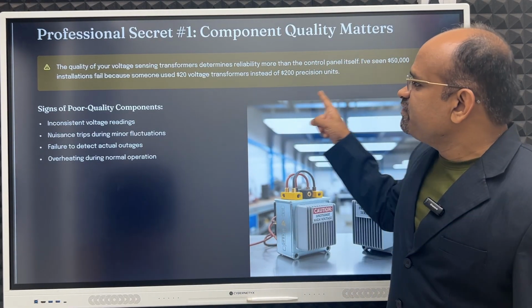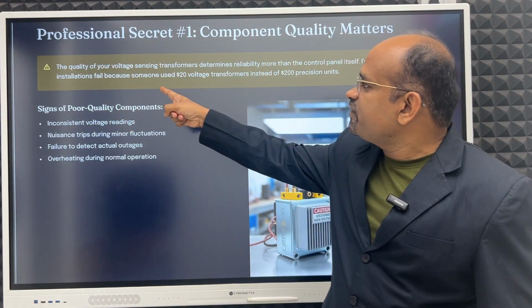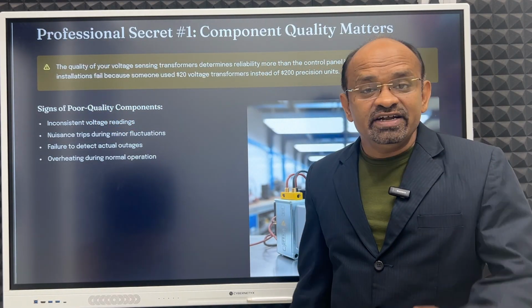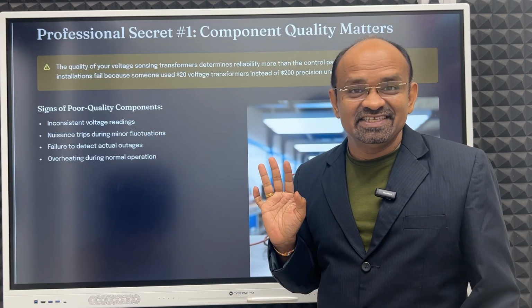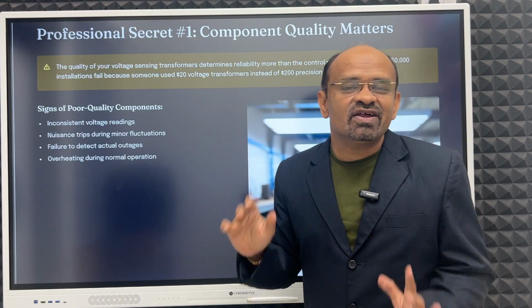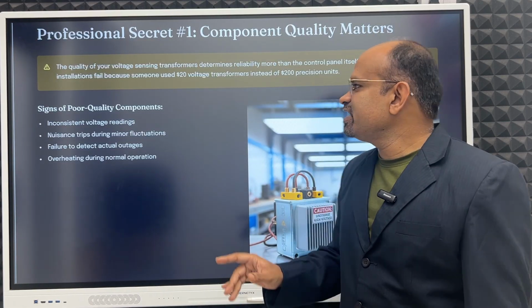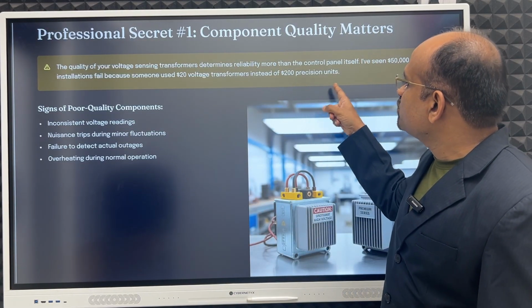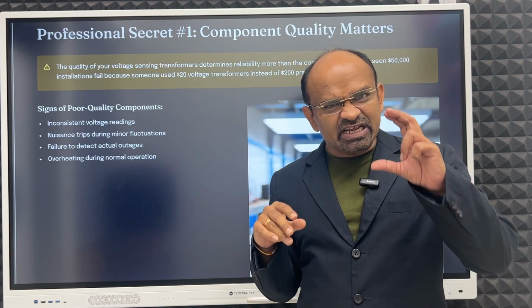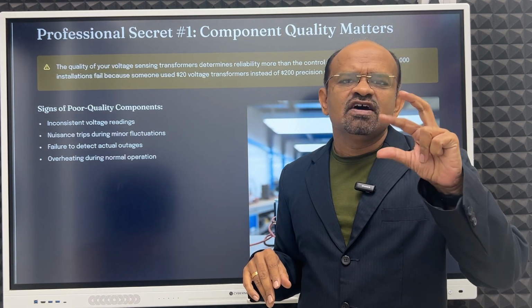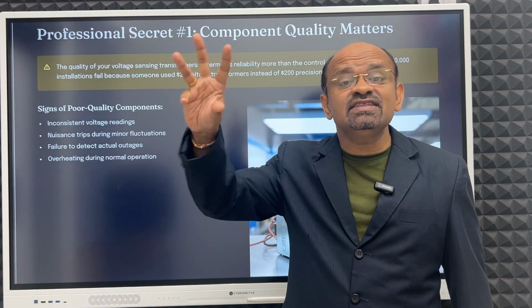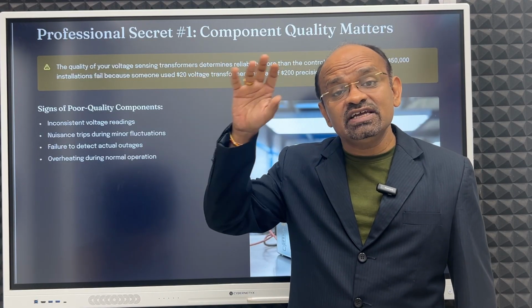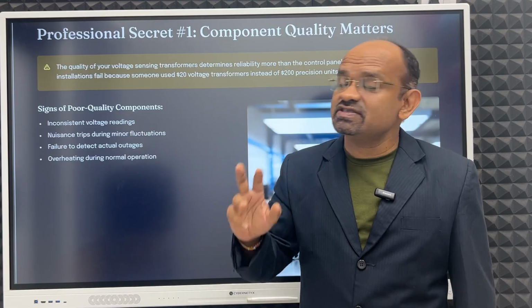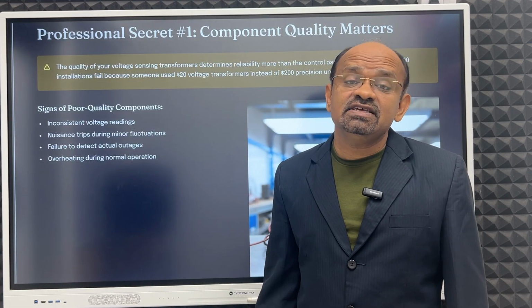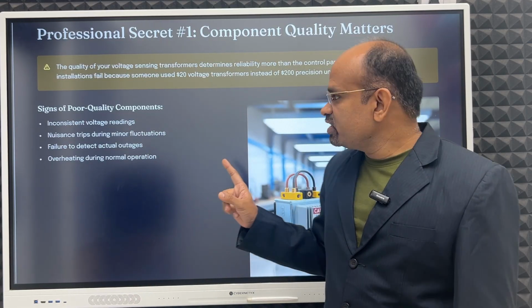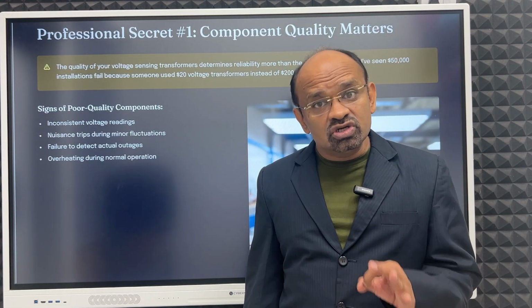I have seen 50,000 USD installations fail because someone used a $20 voltage transformer, a cheap, inferior quality transformer. It will not sense accurately. So precision is important, accuracy is important for this transformer which is sensing the voltage. It senses voltage, frequency and phase sequence. All these three things are sensed by this potential or voltage transformer. So this should be very good quality equipment.